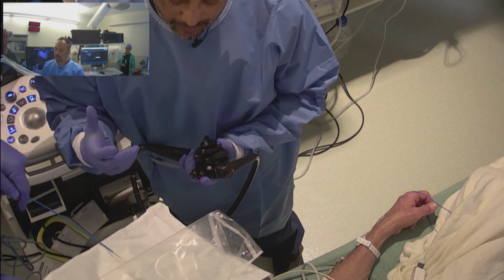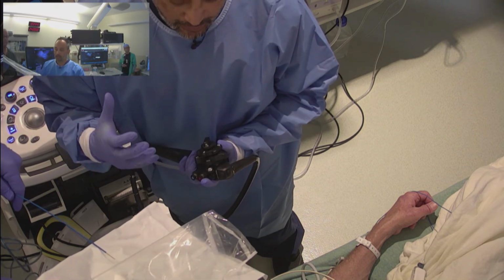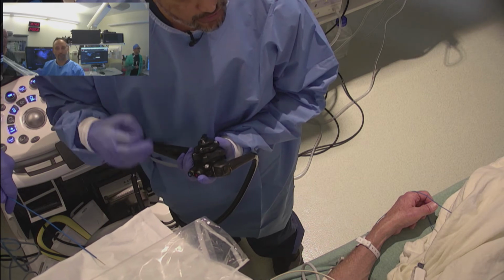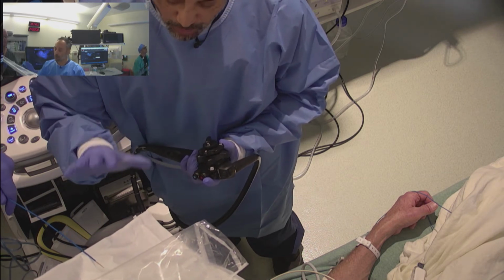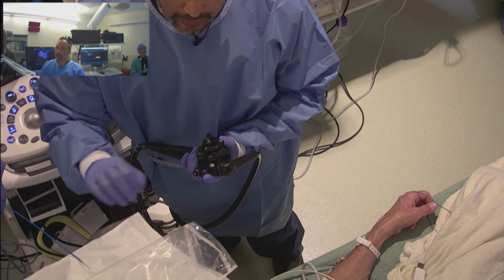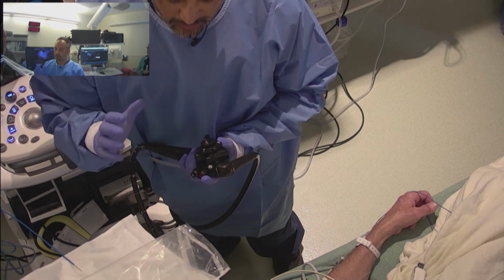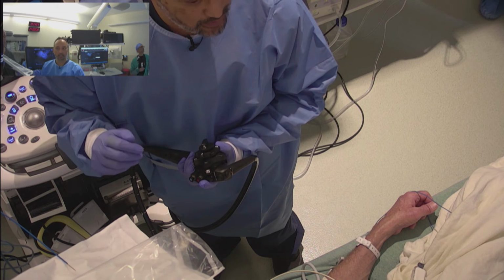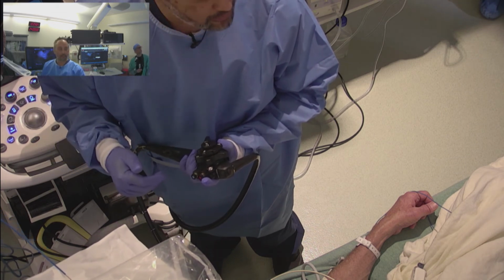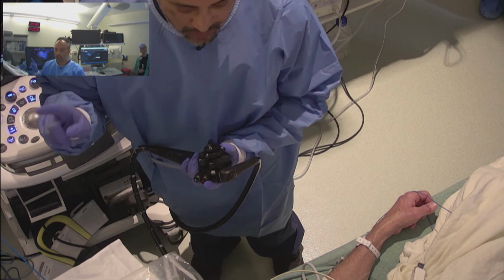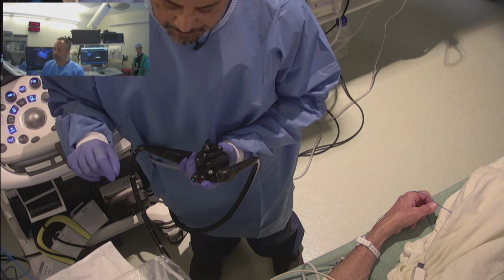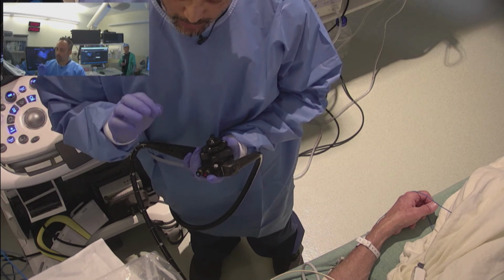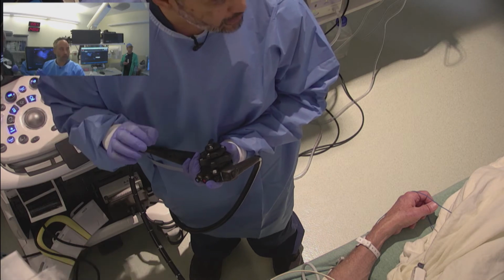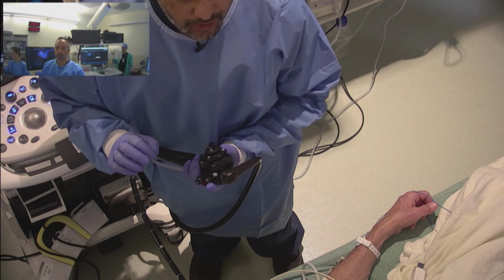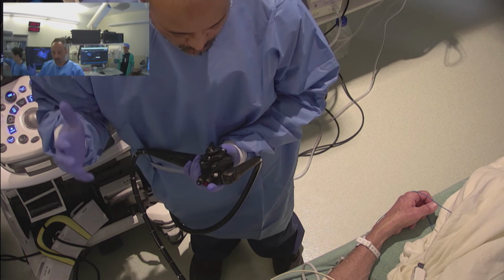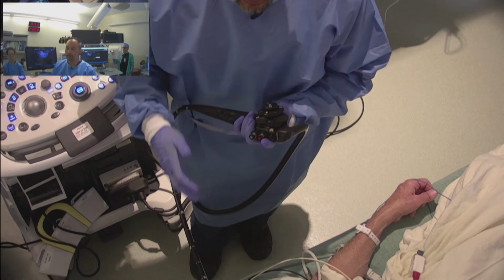So again, 3 different catheter sizes. We use 3 different energy levels based on the catheter size for the ablation zone. For the smaller catheters, so the 5 millimeter catheter, we're looking at an ablation zone of around 6 to 7 millimeters of ablation, and then higher with the increasing size of the catheters. They do have a proprietary generator that delivers the energy. We try to treat with essentially a lower wattage for a short duration. In other words, we're trying to avoid charring the pancreatic tissue, and of course the big concern there is pancreatitis.